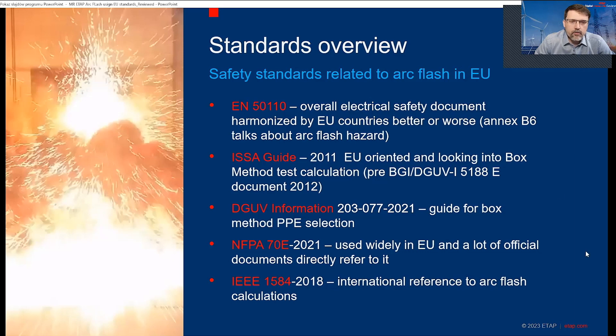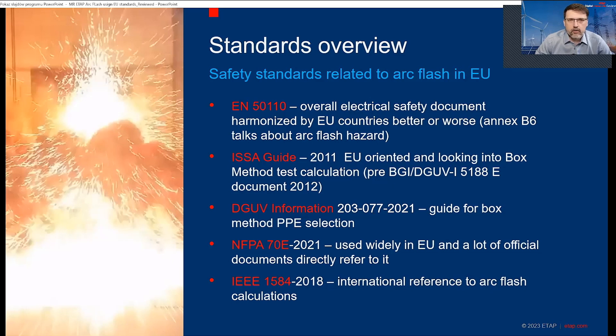The ISSA guide covers thermal arc flash hazard and is kind of the best document so far in the EU, but it was a brief document pre-DGUV release. So generally the DGUV later version is almost the same as what was presented in that guide. Then we have DGUV Information 203-077 — the latest release is from 2021. This standard talks about arc flash PPE selection based on the box method test.